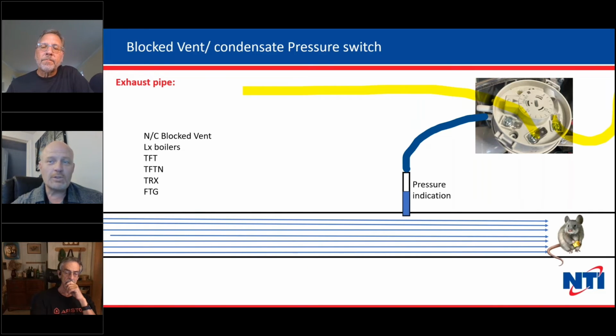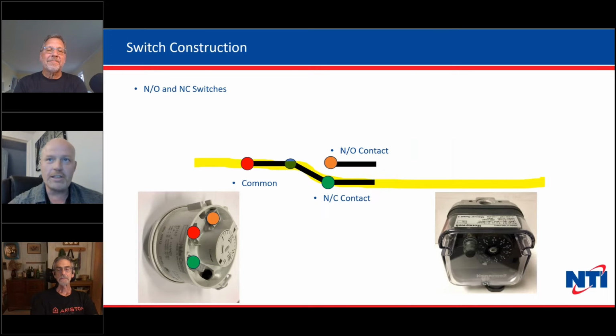However, our favorite little mouse with the cheese gets in the exhaust and dies. And what's going to happen is he's going to create an artificial restriction. It's going to increase the pressure, getting above the set point of the switch and shutting it off. And of course, what's going to happen there is the boiler's going to shut down.